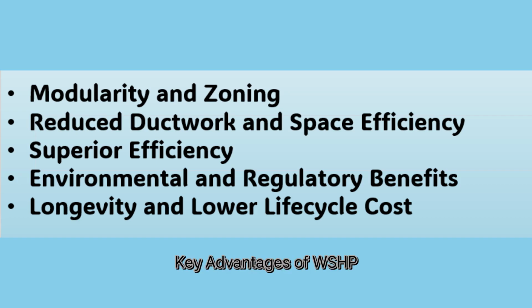Key advantages of WSHP systems: A. Installation and operational flexibility. Each WSHP unit can be installed above ceilings, in closets, or in mechanical rooms. This modular approach minimizes ductwork and simplifies maintenance. Each zone operates independently, though all can still be monitored via a central building automation system, BAS.